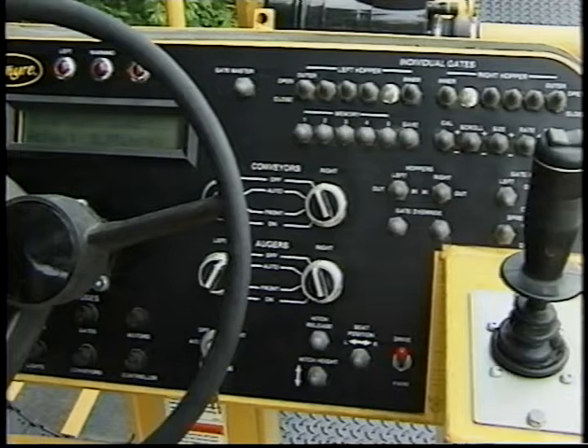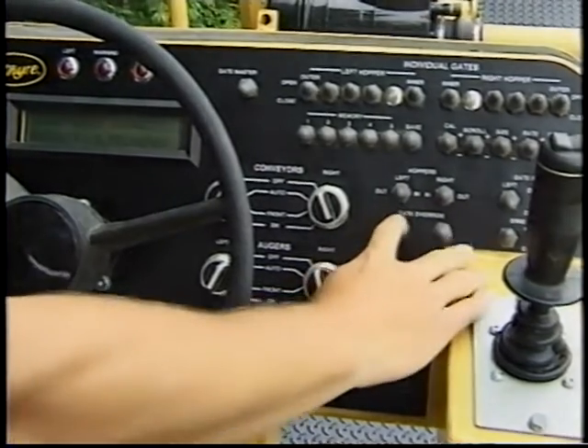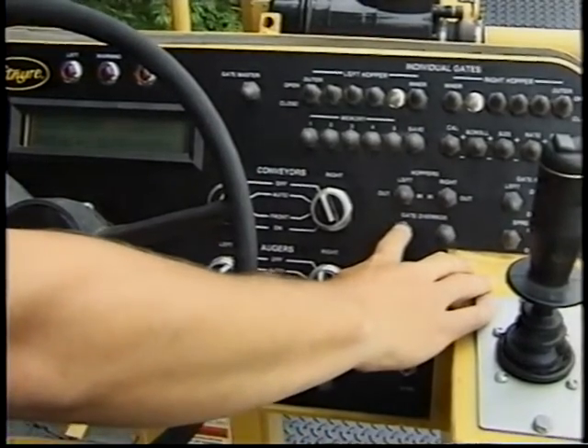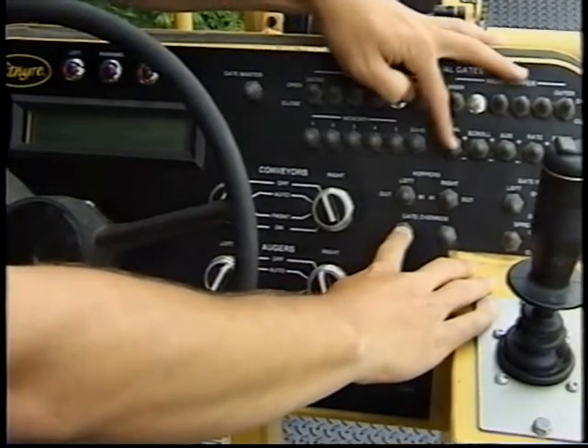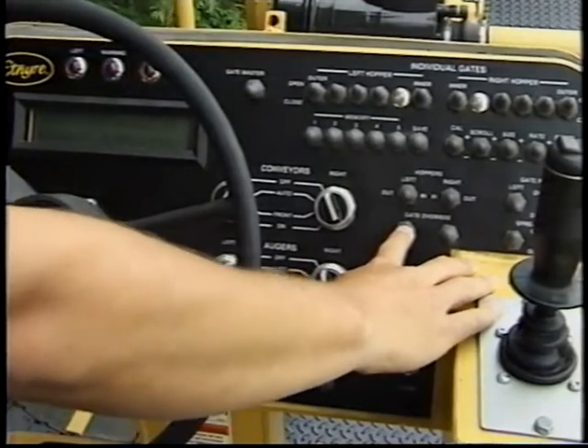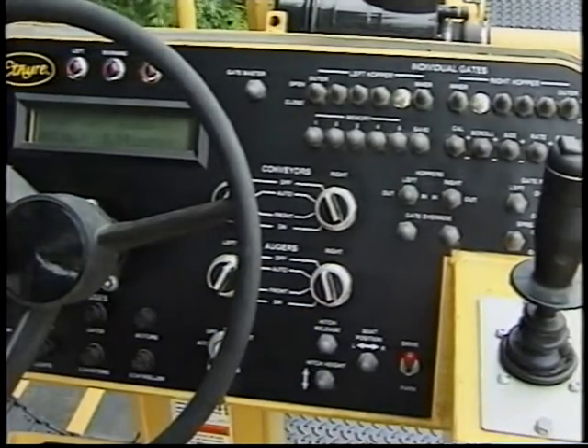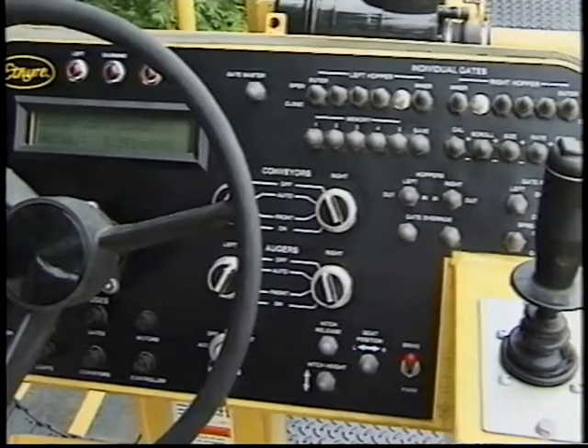This screen is used to set the full open position of the left gate. Depress the left gate override button, and while holding the override button down, depress the CAL switch. When the open position has been set, push the scroll switch down to move to the next screen.